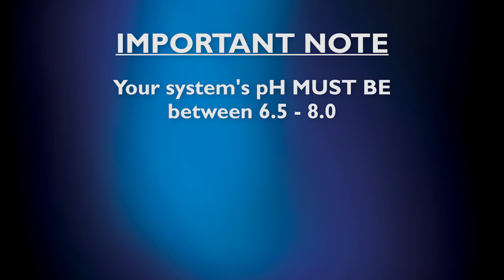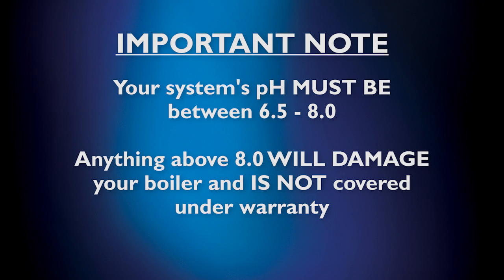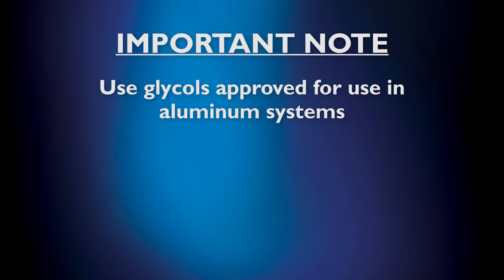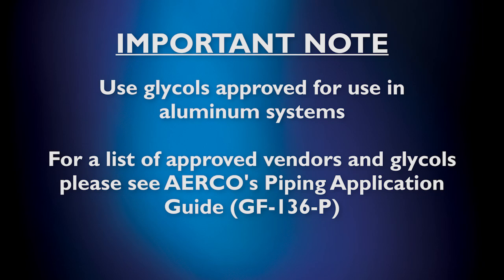Before we go any further, an important note on water treatment. Your system's pH must be between 6.5 and 8. Anything over 8 will damage your boiler and is not covered under the product's warranty. Also, use only glycols approved for use in aluminum systems. For a list of approved vendors and glycols, please refer to AERCO's Piping Application Guide, document number GF-136-P.